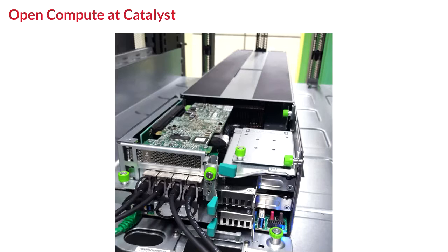In a 42 RU rack, you can fit 54 of those. If you go up to 48 RU, you can fit 63. As with other interesting things you can see, this is an open rack. At the back, you can see those black bars going up. Those are 12-volt power rails, so the servers don't have their own PSUs. They just run off 12 volts.